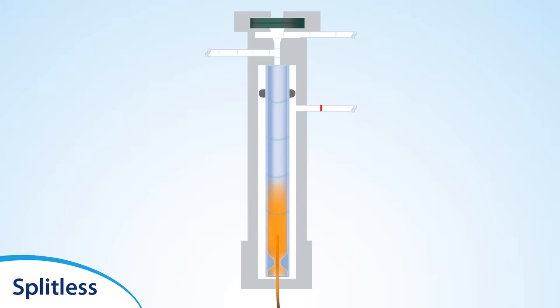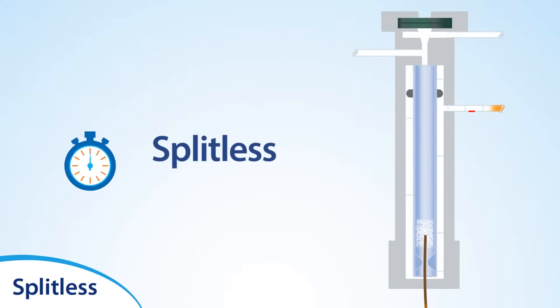Once sufficient time has elapsed after injection, the split vent opens to purge the inlet. This duration, known as the splitless hold time, is calculated to be long enough to allow the maximum vaporization and transfer of analytes to the column.